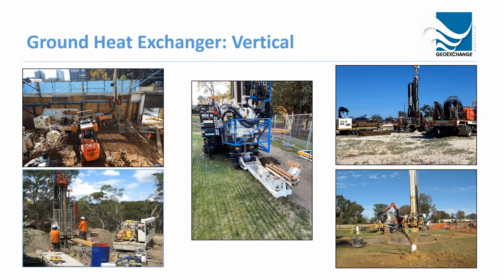There was a lot of water produced through that, so this method allowed us to avoid that, without having lots of water produced at the surface and then having to dispose of it. Granite and basalt and stuff, they're your harder rock types with a high water content. They can still be really useful thermally, it just obviously requires a different approach to the drilling itself. The good thing about a lot of the rock drilling is that you will typically get a very clean open hole to work with. Depending on the rock fractures, there's still some management of that hole, but a lot of the time you'll have a really clean hole. The loop will go down really easily, with very little issues.